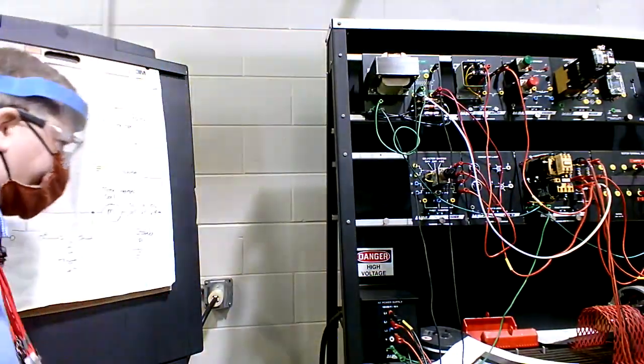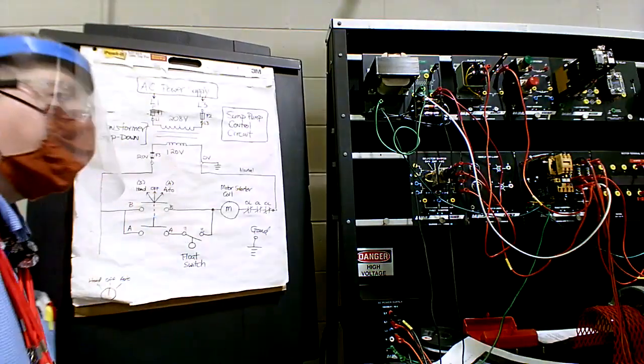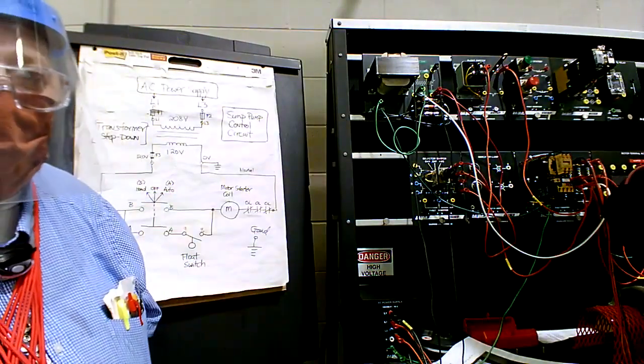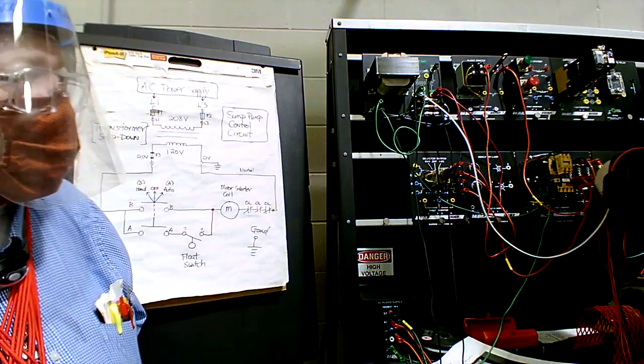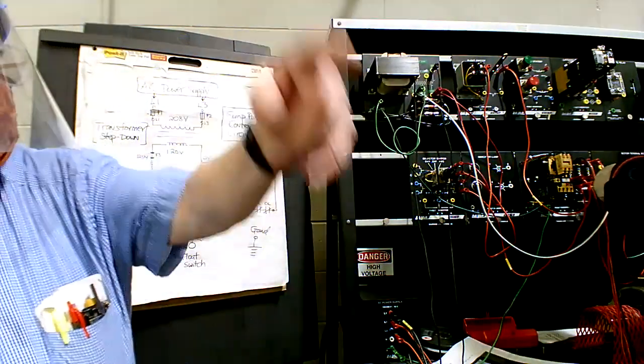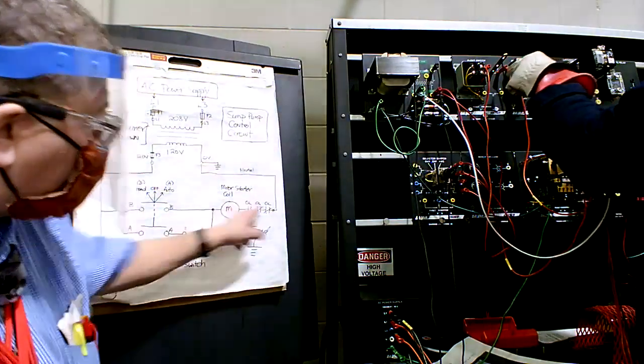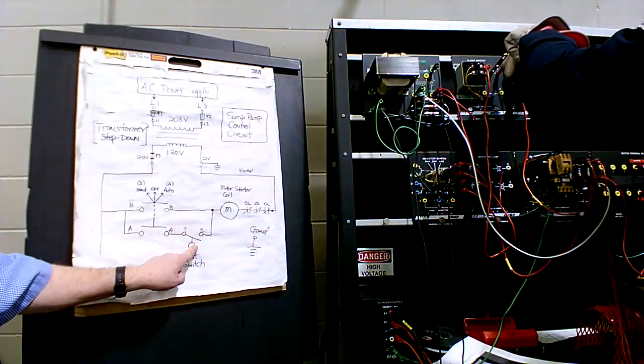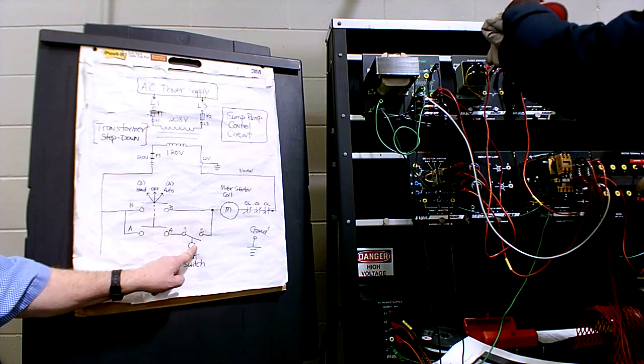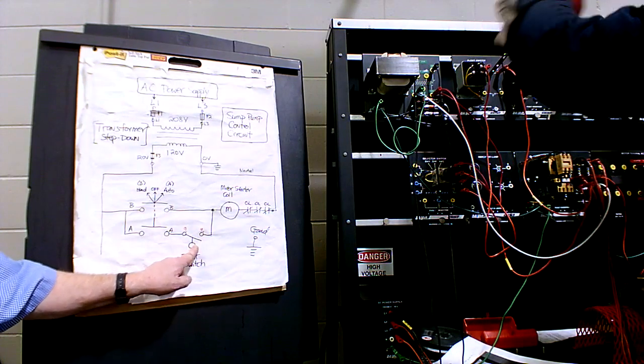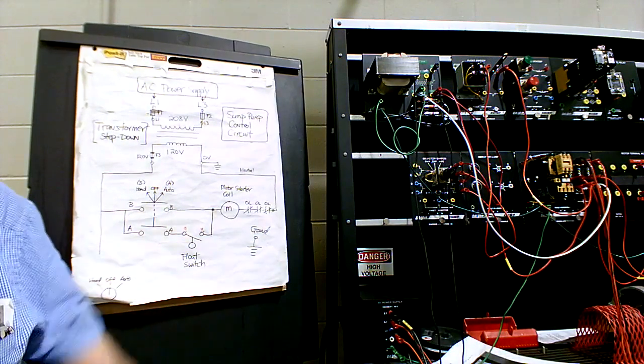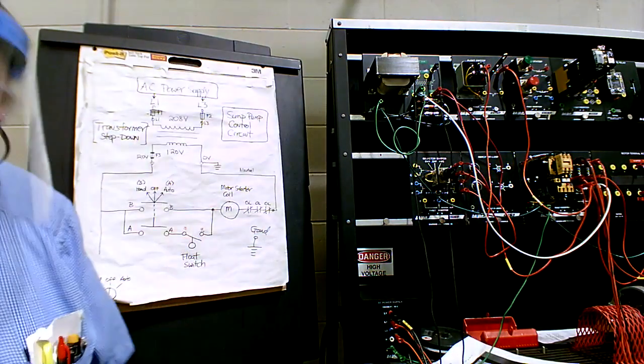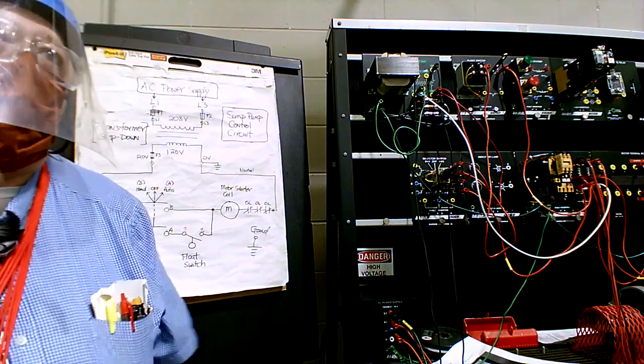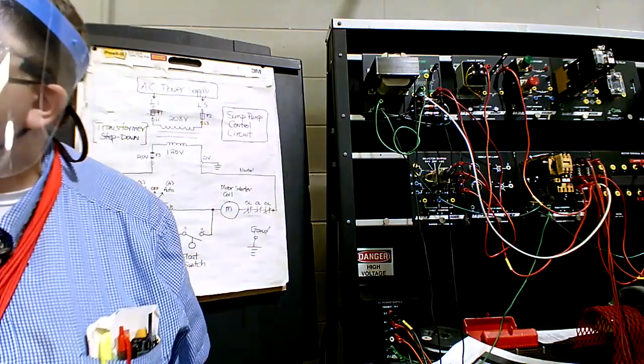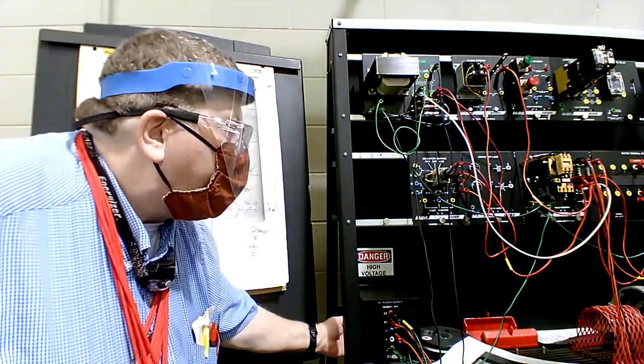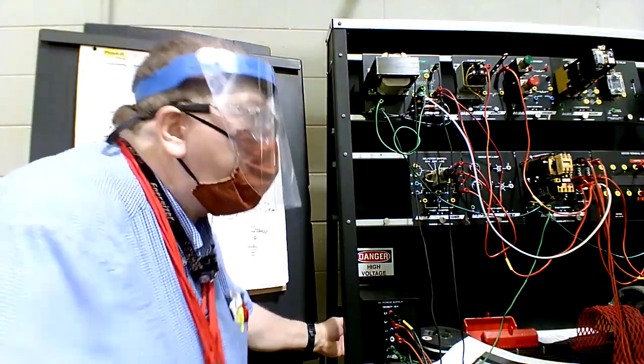Now cut it back on. Now, read your voltage again, and hold the meter up where everybody can see. You're getting 120 now across it because I put a brand new contact in there, okay? Fixed it. I've got fault switches I can put in, and it actually puts resistance in there behind the board. Anyway, that was it. That's a bug for low voltage on your control device. Just bad contacts, okay? And anyway, so that you can do your measurements here.